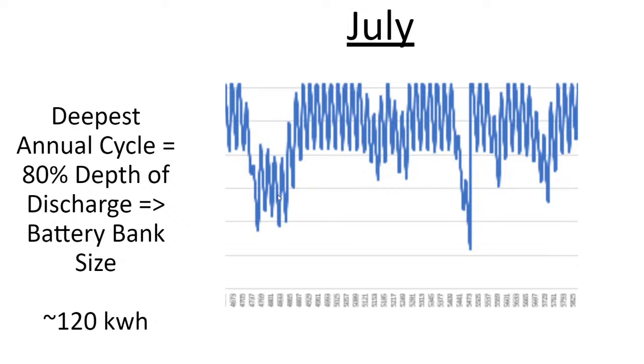Batteries perform better when they're not fully utilized. Whether it be a lead acid battery that has a reputation for, don't discharge that battery all the way or it won't charge back up again. Even lithium ion batteries have the same thing where, if they operate towards the very bottom of their range, they take more damage on their anodes and cathodes than if they are operating up at the top of their full state of charge.